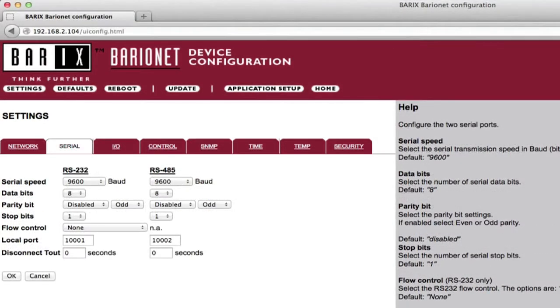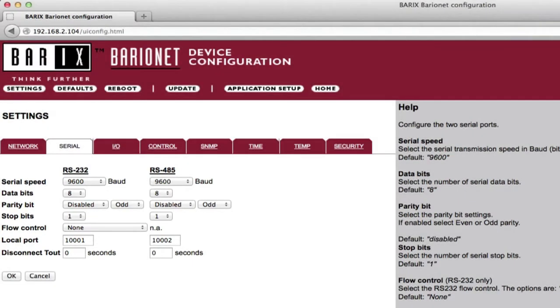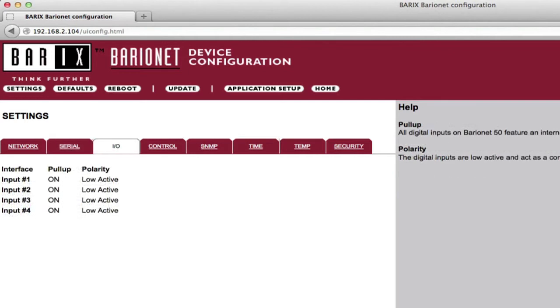The Serial Settings page allows setup of the configuration parameters for the serial interfaces. The Barionet 50 has RS-232 and RS-485 configuration options, while the Barionet 100 also includes options for the RS-422. As the inputs are fixed, the I/O settings page on the Barionet 50 does not have any user-configurable parameters. The Barionet 100 does allow I/O configuration.